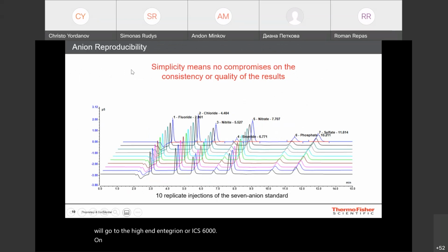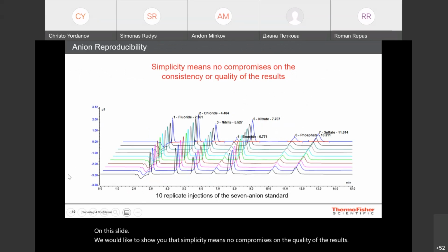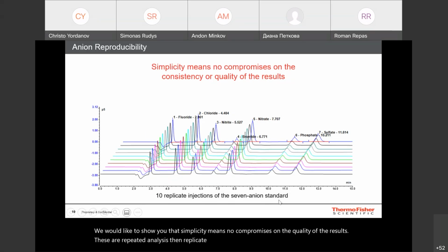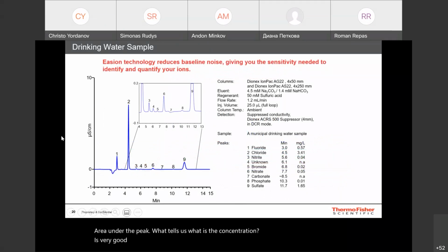On this slide, we would like to show you that simplicity means no compromises on the quality of the results. These are repeated analyses, 10 replicate injections of the 7 anion standards. And if you compare all these chromatograms, all the peaks, it looks pretty much the same. Reproducibility of the retention times, which tells us what ion it is, and area under the peak, which tells us what is the concentration, is very good with this kind of instrument. Gives us reliable results.